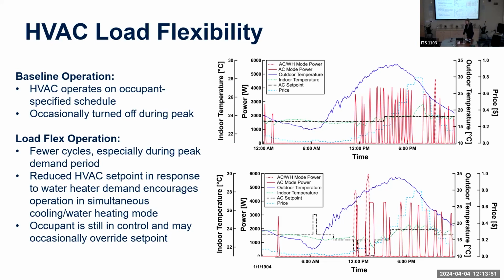So to give you an idea of how this looks for HVAC load flex and water heating load flex, this is the HVAC portion. So for baseline operation, we're operating the system on an occupant specified schedule, and the system is occasionally turning off during peak because this particular homeowner is enrolled in OhmConnect. So any load shift savings that you see are actually on top of what's already taking place with OhmConnect. For the load flex operation, which is on the bottom plot, you can see the system cycles a lot less frequently as compared to the baseline day. And if you look around 7 a.m., that is one instance where the user maybe raises the set point periodically. And then right before noon, you can see the reduction in set point. That's one of the simultaneous AC and water heating cycles.